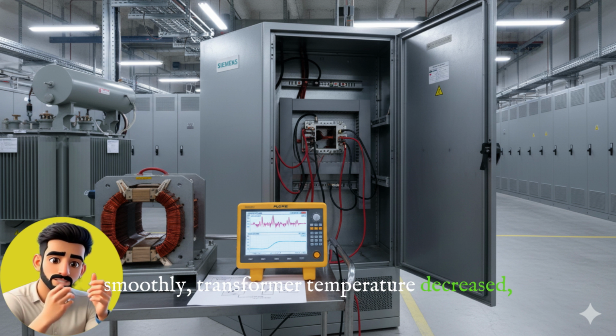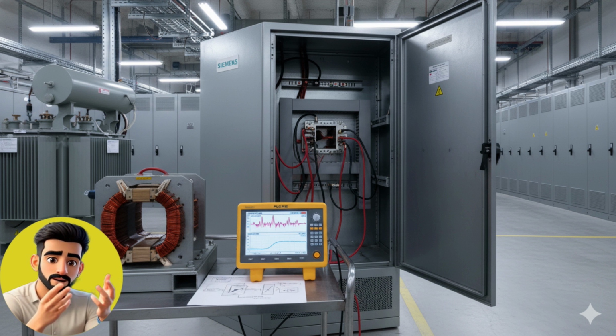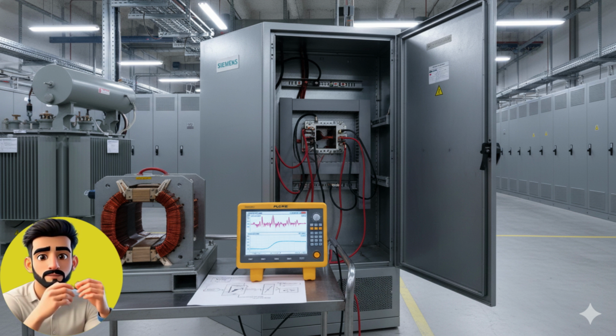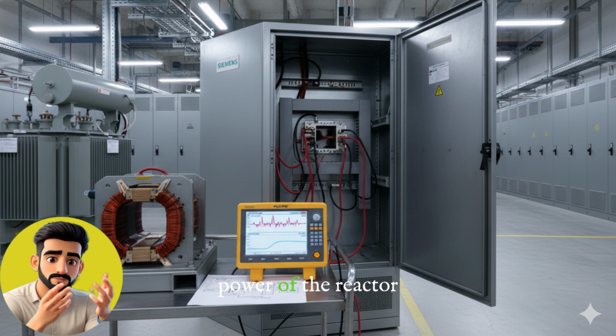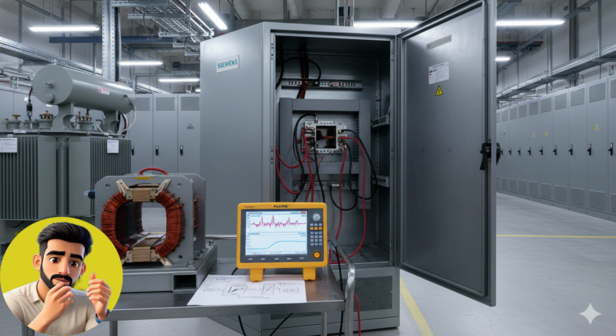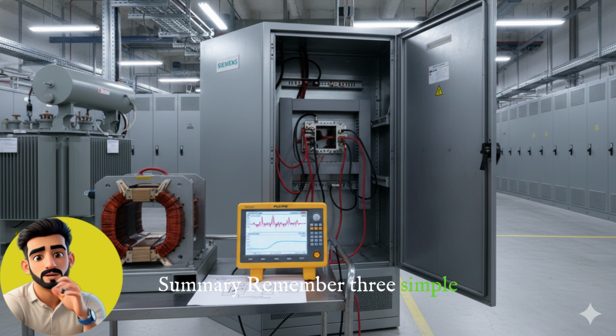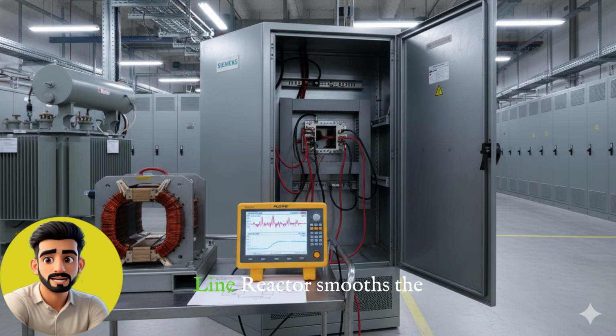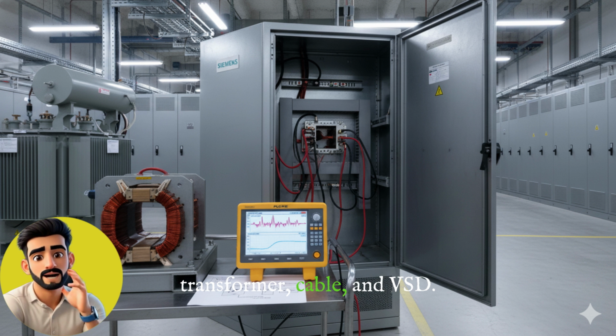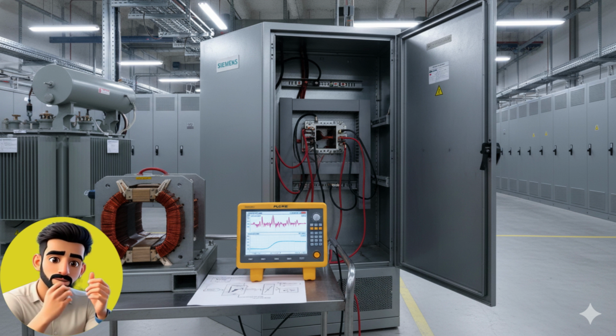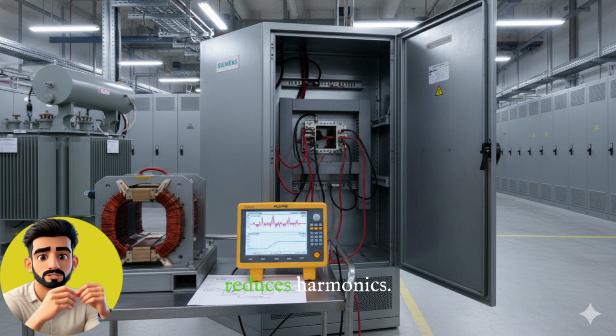Transformer temperature decreased, current waveform became clean, and trips almost stopped. This is the true power of the reactor and choke. Summary: remember 3 simple lines. 1. Line reactor smooths the input current. 2. Line reactor protects the transformer, cable, and VSD. 3. DC choke stabilizes the DC bus and significantly reduces harmonics.